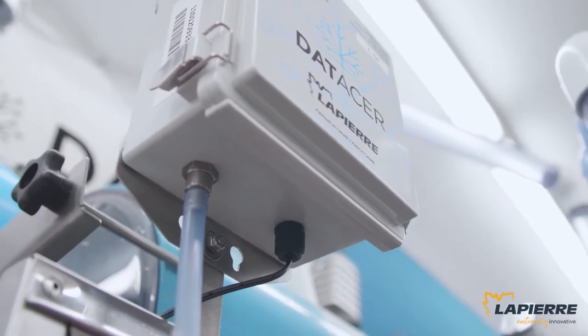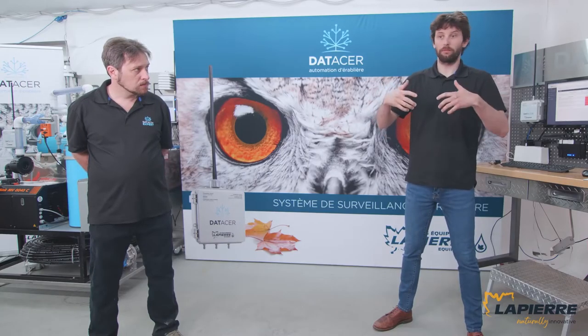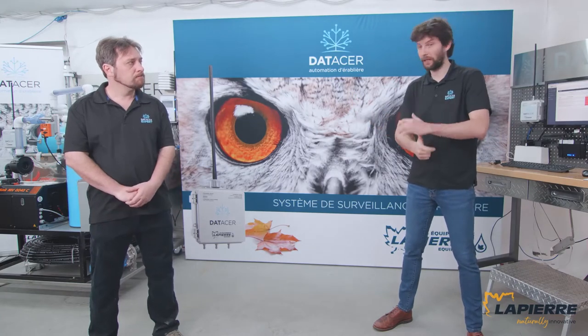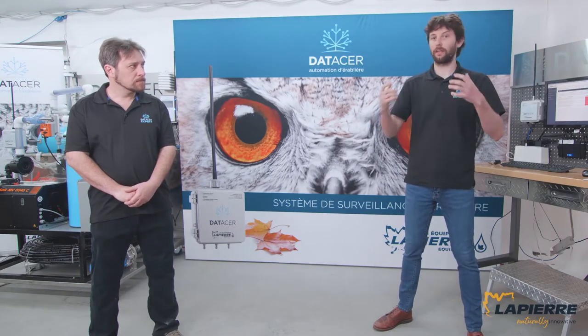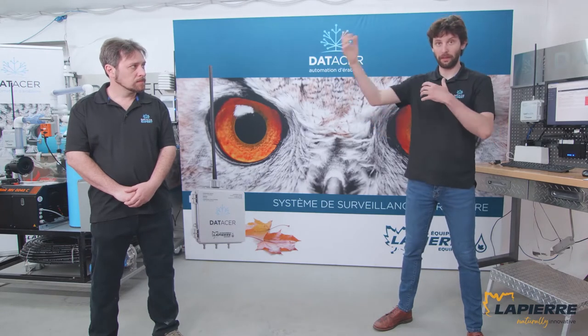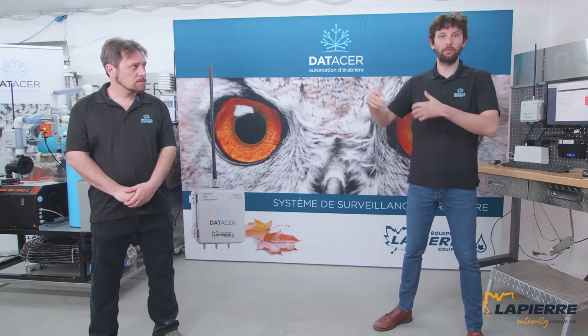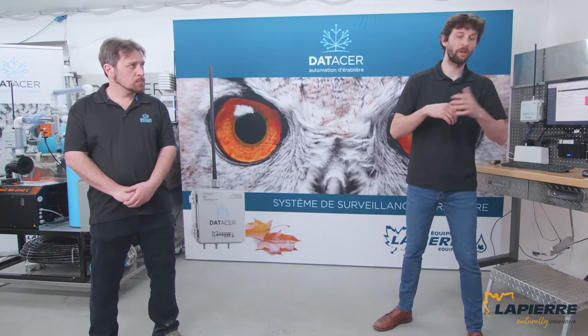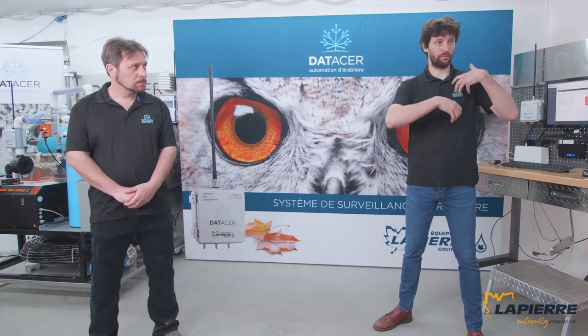The first group of functions is to monitor different kinds of parameters, like vacuum at the end of lines and vacuum at your extractors. That way, you can calculate the differential between them, which is really useful to know if you are tight enough. Then you can measure tank level, and pressure for a pump or concentrator. You can measure temperature, outside and inside, and so on. You can also know if your equipment is properly working, if your sap pump or your transfer sap pump is currently running.